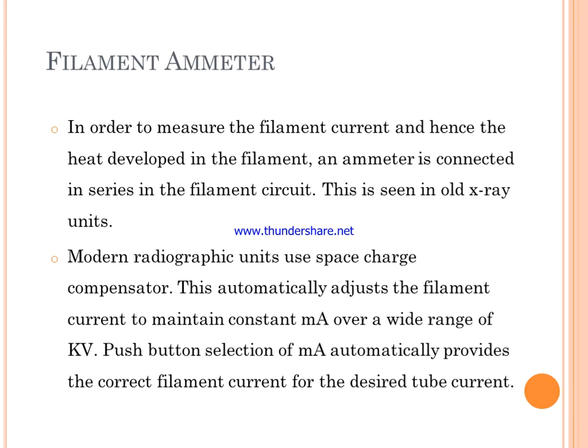The filament ammeter measures the filament current and the heat developed in the filament circuit. This is seen in older X-ray units. In modern radiographic units, a space charge compensator is used, which automatically adjusts the filament current to maintain a constant mA over a wide range of kVp.